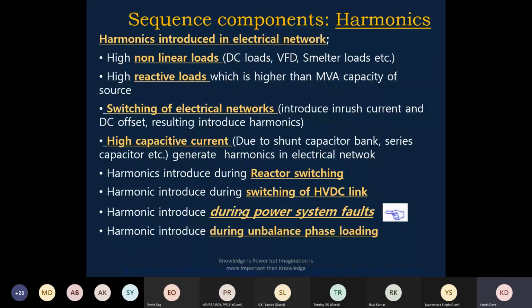Switching of electrical networks, like transformer charging, then any breaker closing, then motor starting, capacitor switching, inductor switching. So any switching of electrical networks introduces the harmonics. High capacitive current. Yes, shunt capacitor bank starts. That is called the high capacitive current.